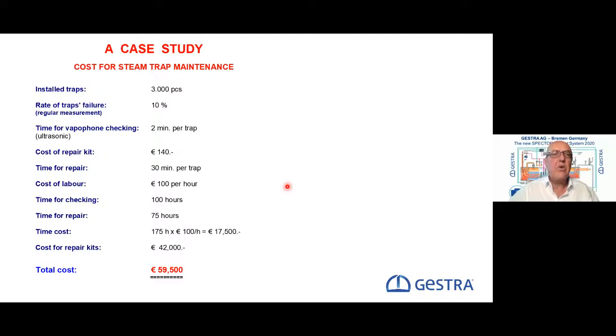problematic there. And if we do it a different way and say, no, we make an annual test of our steam traps, we want to find out which are the faulty steam traps, we build in a new bimetallic regulator, or we clip on a new capsule, or sometimes also a ball float trap regulator maybe, then we can say we have the same company with 3,000 pieces of steam traps installed. The annual steam trap failure rate is 10%, which we find out. With the ultrasonic check, which is offered by our opcos everywhere in the world, it needs round about 2 minutes per trap if we make it regularly.